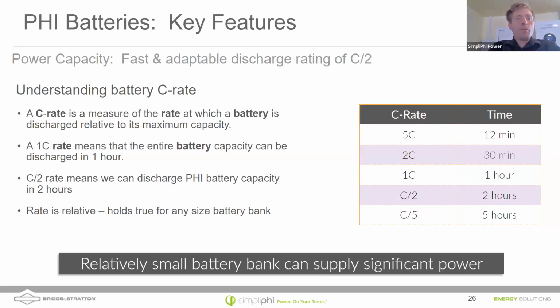So the C rate of a battery is a measure of how fast the battery is able to charge or discharge relative to its maximum capacity. So it's a ratio of the capacity to the maximum charge or discharge rate. A 1C rate, of course, means the battery could be discharged in an hour. A C/2 means 2 hours, and a typical number is C/3 for many lithium batteries. Ours are a little bit faster at C/2.